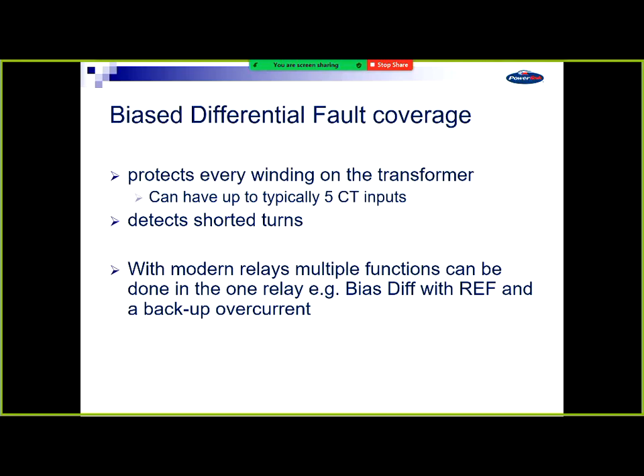So you can have up to about 5 CTs in these transformers. So what that would be is if you've got a breaker and a half on one side, breaker and a half on the other side, and a tertiary, and you've got all your CTs brought in individually, that's 5 CTs. So you can protect a transformer like that. Do you know what I mean when I say breaker and a half? One nod, couple of nods.